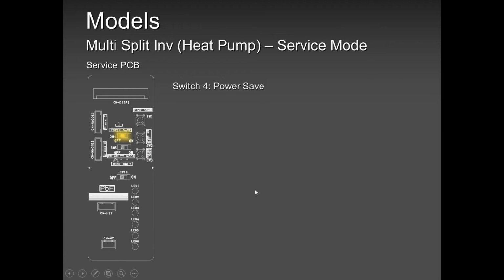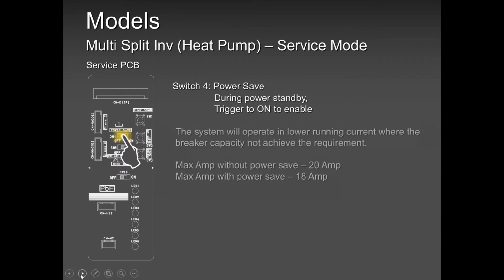Then comes the power save button. If you have spent a lot of money to buy this big system, I don't know why you want to use the power save button, but if you want to use it, you are more than welcome to. So basically what power save does, it runs the frequency of the compressor at 75% instead of running at 100%, which means the compressor will not ramp too high. So if your neighbor is complaining it's too noisy, you can do that. Or if you have a big system but very small indoor units and it doesn't need that much power, then you can do that too.